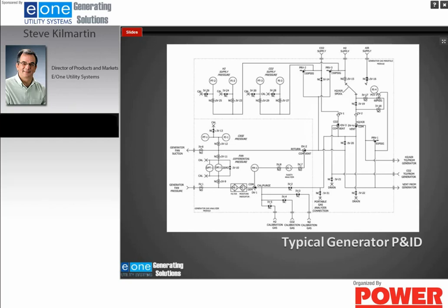Now, if this was not connected across a generator fan and was just connected to the case, the three-way valve on the outlet of the analyzer could be turned towards vent, and then the flow would exit the analyzer and go to vent versus return to the generator, and you would be using some hydrogen to measure the purity. So under normal operating conditions, you have your hydrogen coming from across the fan in the generator.